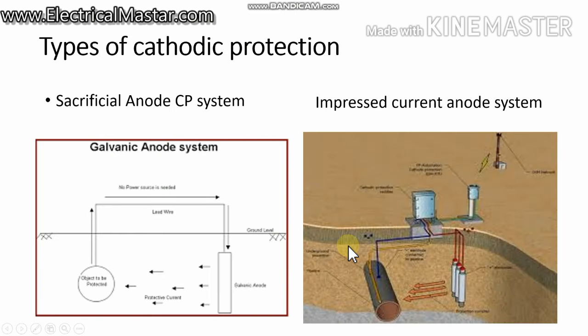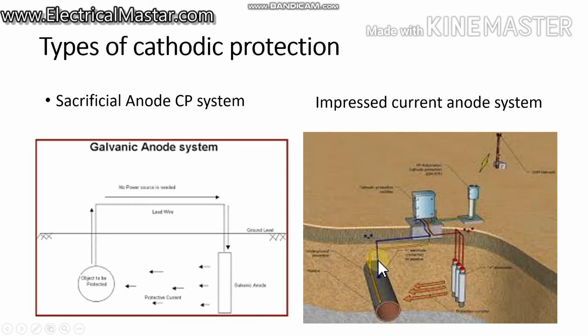Next, let's see what types of cathodic protection are available. There are two types: one is the sacrificial anode system, and the other is the impressed current anode system. In the impressed current anode system, we apply an external DC supply to the anode; the anode loses positive current to the metallic structure and it returns back to the source. This is the method we have been discussing, and it is mainly used in the oil and gas industry.